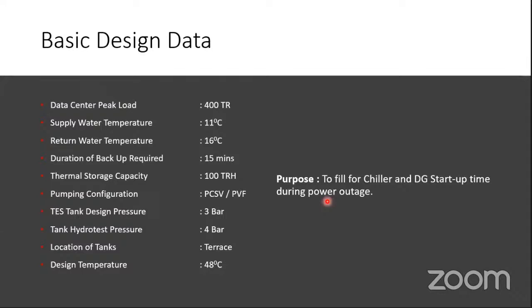This duration generally is in a range from 5 to 15 minutes of backup. And these are the tanks which we call low volume systems. The previous one for demand management that we saw, they were high volume systems. They were large tanks, and these, for this particular application, can be termed as a low volume application.